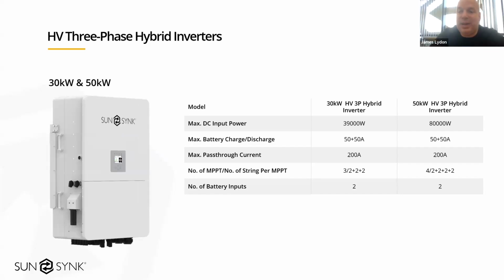So yeah, the 30 and the 50. As I said, these have both got two HV battery inputs on. The batteries, which I'm going to come to on the next slide, each stack is up to 61.4 kilowatt hours per cabinet. And you can actually have 16 cabinets connected to one inverter. So if you imagine you can parallel 10 50 kilowatt hybrid inverters, and each of those paralleled inverters can have 16 batteries, the possibilities are pretty endless on it. It's massively scalable.